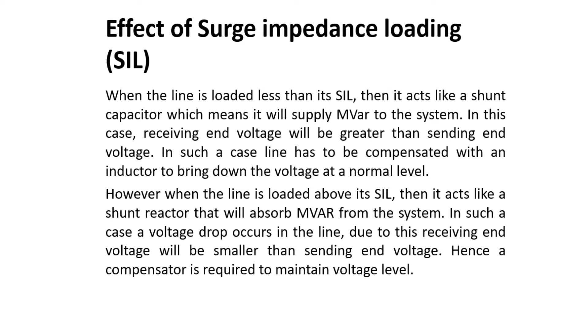But below the surge impedance value, that is from R5 to R7, we have inductive behavior. Therefore the receiving end voltage is less than the sending end voltage. When the line is loaded above its SIL, it acts like a shunt reactor that will absorb MVAR from the system. In such a case a voltage drop will occur, as the receiving end voltage will be smaller than the sending end voltage. Hence, a compensator is required to maintain the voltage level.